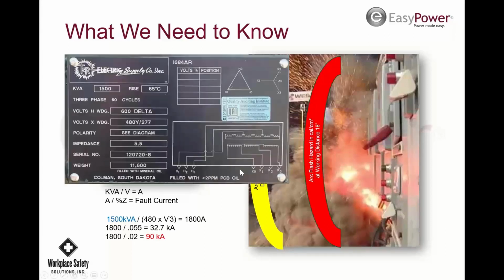Another form of impedance is the transformer. So this is a transformer nameplate, and impedance is on the transformer itself. So the 480 volt secondary, it's a 1500 kVA. I did some calculations down here, so we've got 1800 amps of load potential from this transformer. And if you calculate out the kVA rating of this particular transformer, the bolted fault current rating is 32,000 amps roughly. Older transformers will have a lower impedance, and if you have a lower impedance, you're going to have more fault current. So this gives you an idea: a 2% impedance with an older transformer would be 90,000 amps of fault current. So that's going to have a pretty big impact on what your levels are as you go and you do your study.